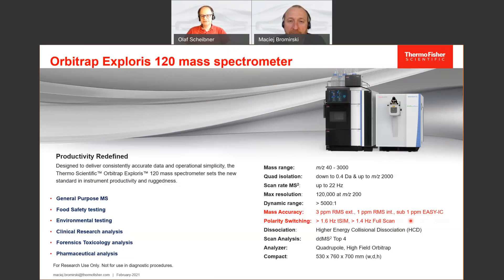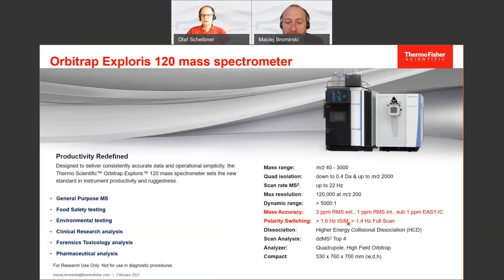On the other hand, there is polarity switching on this system, which is better than 1.4 hertz if you run in full scan. This means that we run a full scan in positive mode, switch to negative mode, run a full scan in negative mode, and switch back to positive mode. This full cycle gives you a scan rate of 1.4 hertz on both polarities each. This is the fastest polarity switching that exists on high resolution mass accuracy instruments, and it gives you great opportunities in the analysis of complex samples.